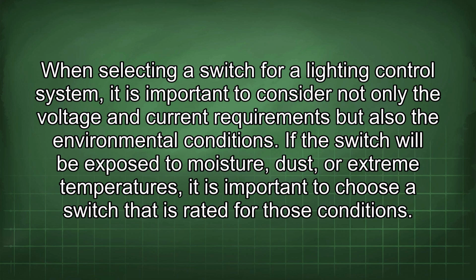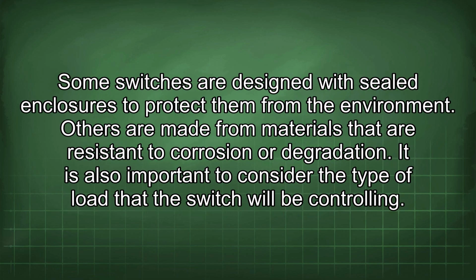When selecting a switch for a lighting control system, it is important to consider not only the voltage and current requirements but also the environmental conditions. If the switch will be exposed to moisture, dust, or extreme temperatures, it is important to choose a switch that is rated for those conditions. Some switches are designed with sealed enclosures to protect them from the environment. Others are made from materials that are resistant to corrosion or degradation.